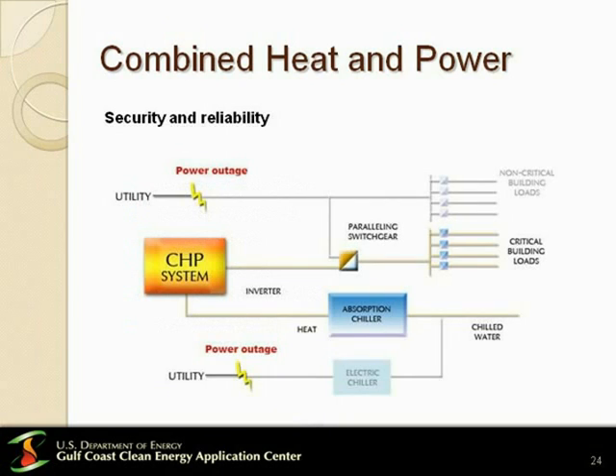In terms of security and reliability, this slide shows how your CHP system connects to your facility. It's typically connected through a parallel switch gear, so you have your utility lines and your CHP electric feeders going through a switch gear and serving the building. Now let's assume there's a power outage - you can see the marks in yellow showing the grid is down. When the grid is down, the CHP system continues to operate, serving the critical building loads. Through an absorption chiller you still get chilled water, and you can meet the heating and cooling needs of your building.